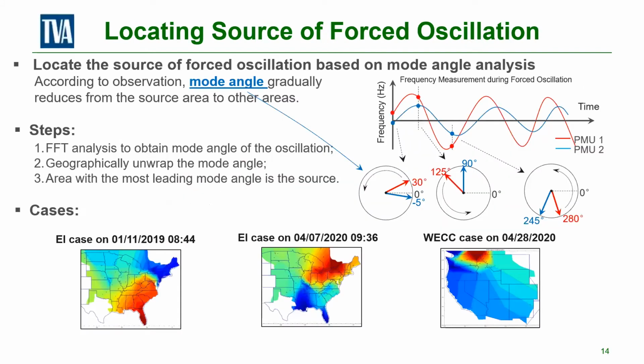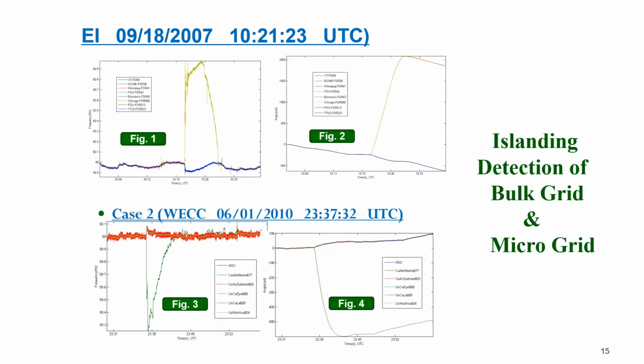So one of our applications is basically to be able to pinpoint the source that's causing the oscillation. You basically take the measurements, you look at all the different areas and you piece out the phase angle of a particular mode. And then you know the power goes from the higher angle to the lower angle. And that's also true for that particular mode. The oscillating power goes in a certain direction. So you can pinpoint the source and you can take action. In the Florida case, they shut down the generator. Someone turned it off, which lasted 20 minutes actually.